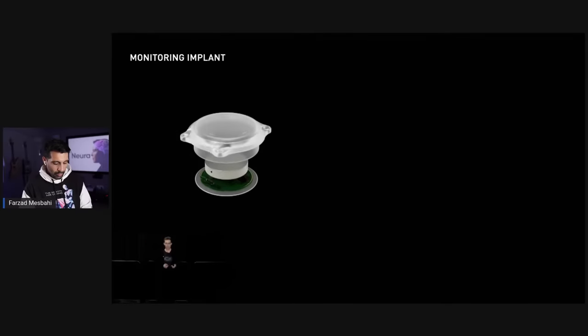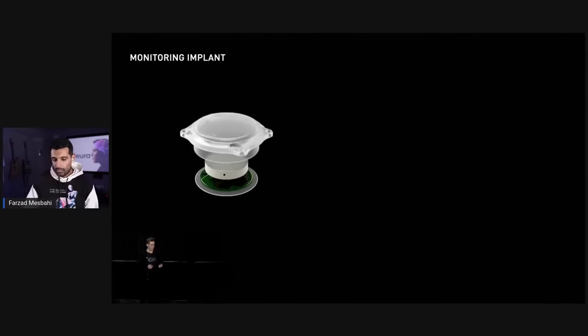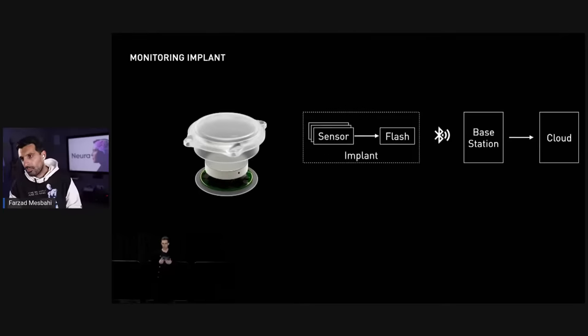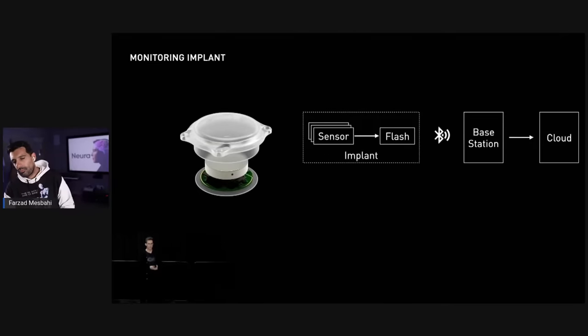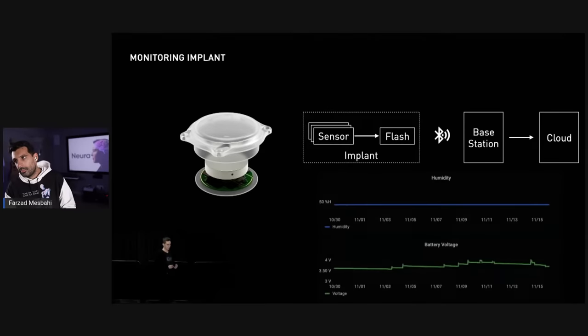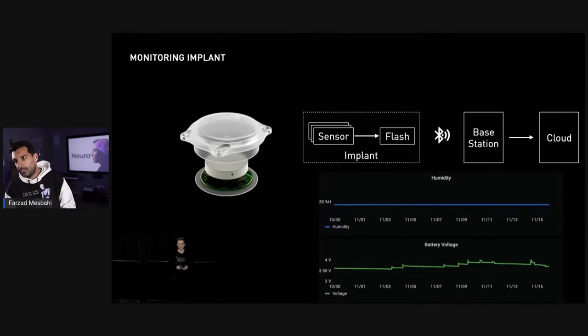Let's look next at how we monitor the implant's electronics, the battery, and the enclosure. The implant periodically captures all of its vital signs and commits those to flash. Then upon next connection with one of our recording stations, it streams that data off. For instance, by looking at humidity, we can get an understanding of the integrity of the implant's enclosure. And by looking at battery voltage and power measurements, we can gauge battery health. All of this is done automatically without any intervention, giving us 24/7 visibility into the quality of every single device.